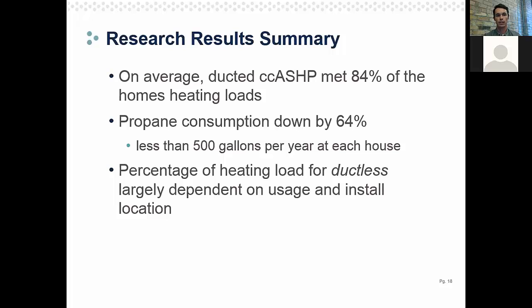So a customer can fill up their propane tank when prices are lower during the summer and then know that they won't have to refill their propane tank over the winter because the heat pump is meeting the majority of their heating load. So that was another big benefit for that system. With ductless systems, it's a little more refined on the design for how much of the heating load and savings you will deliver.